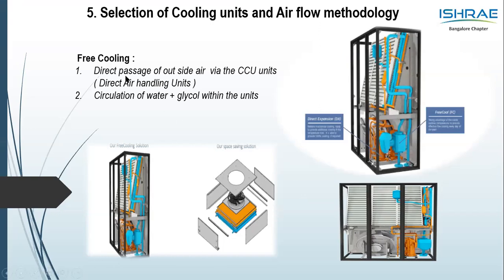So one way is direct passage of the outside air via the CCU unit, but you will have to keep a check on what type of air or where the data center is placed, so that we don't want any kind of high contaminated air or high CO2 air to enter, and also have a check on the type of filter which goes into this CCU unit.